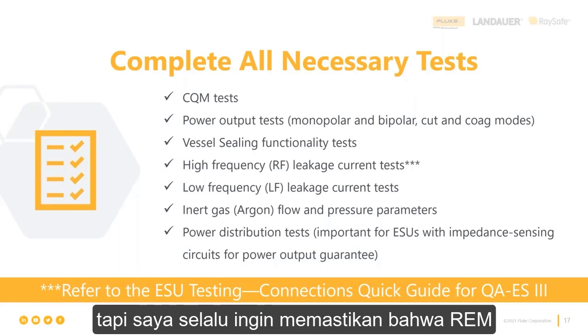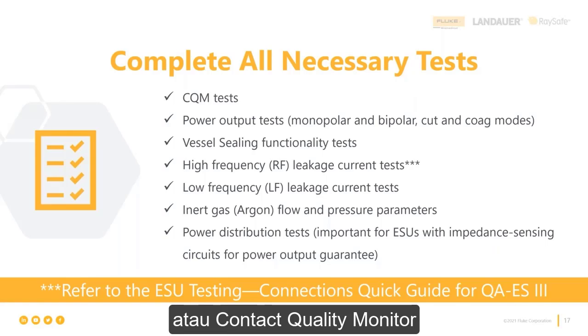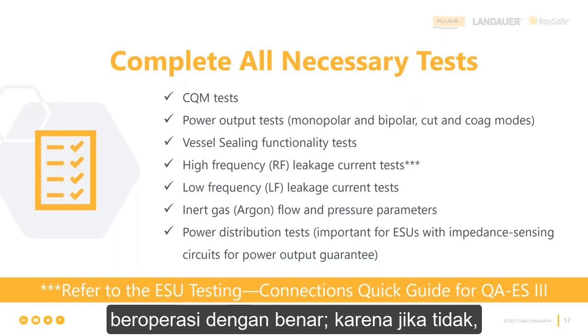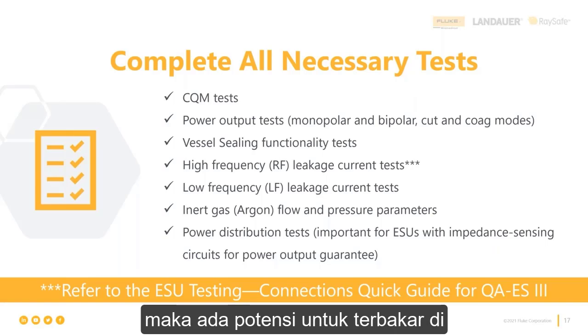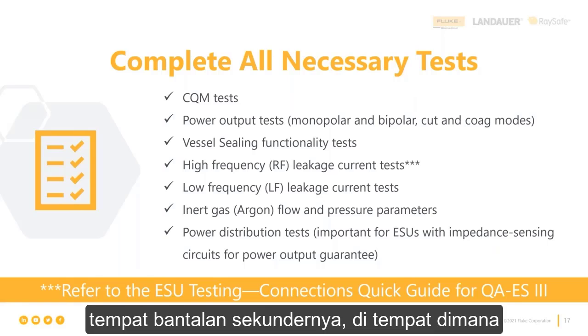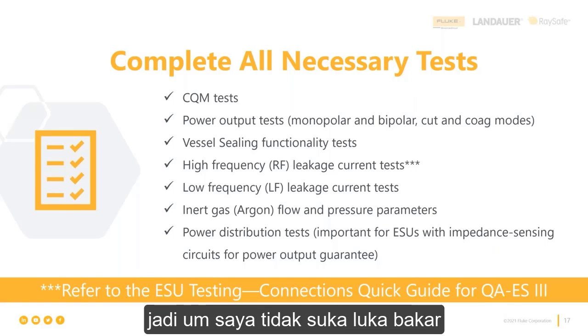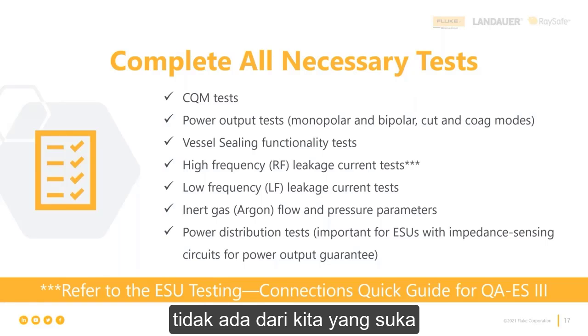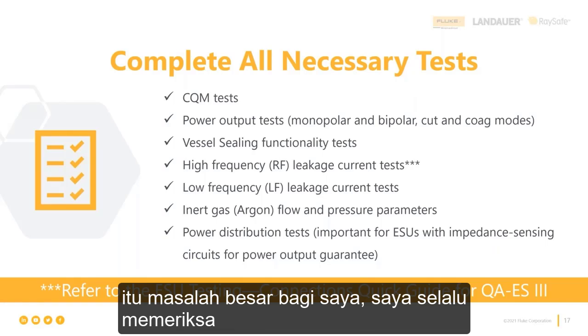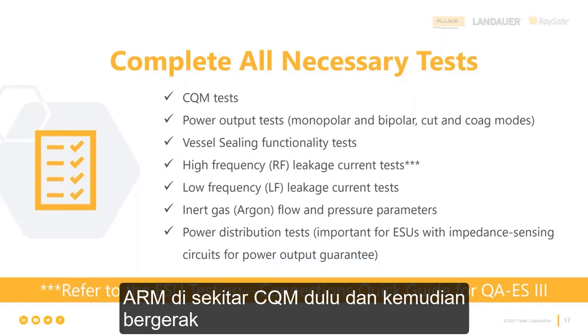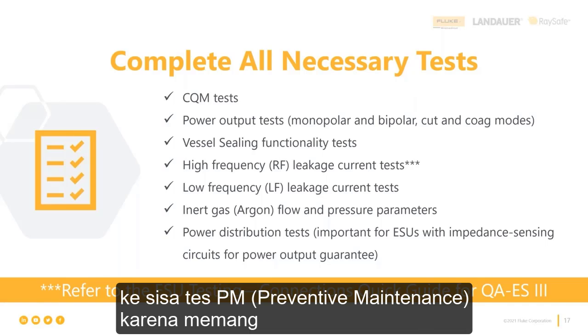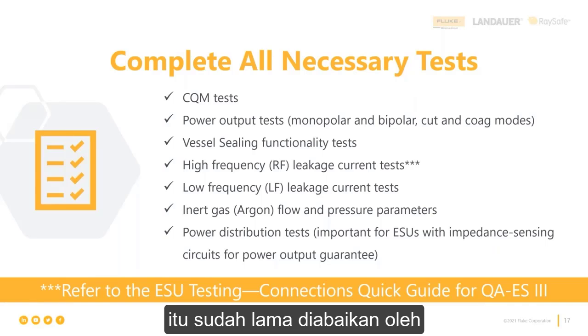But I always want to make sure that that REM or ARM or contact quality monitor is operating properly, because if it's not, then there's that potential to get burnt on a secondary where the pad's attached to you. So I don't like burns. No, none of us do. So that's a big deal for me. I always check that ARM or REM, CQM first, and then move on through the rest of my PM, because it's been overlooked for a long time by a lot of shops.